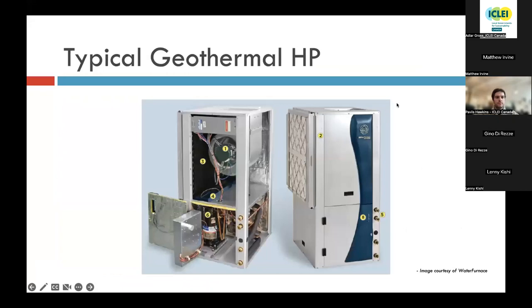So a typical geothermal heat pump looks like this. You've typically got the refrigeration and compressor bearing portion of the unit on the bottom. That would be the compressor, the coaxial heat exchanger, that's the heat exchanger that connects the earth loop to the heat pump, a reversing valve, a TX valve, all of the refrigeration components with the exception of, in this instance, the air coil, which is number three in that picture. That is the heat exchanger that the heat pump uses to put heat into the airstream or remove heat and moisture from the airstream and air conditioning. And of course, there's a fan in the upper section of that heat pump to circulate the air.